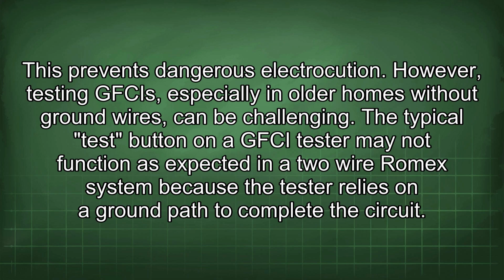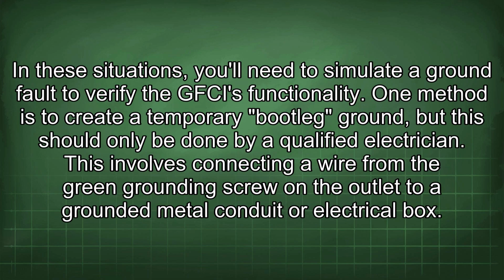However, testing GFCIs, especially in older homes without ground wires, can be challenging. A typical test button on a GFCI tester may not function as expected in a two-wire Romex system because the tester relies on a ground path to complete the circuit. In these situations, you'll need to simulate a ground fault to verify the GFCI's functionality.